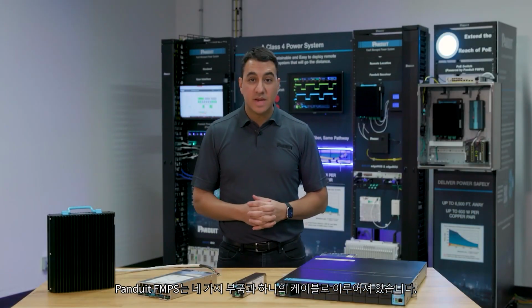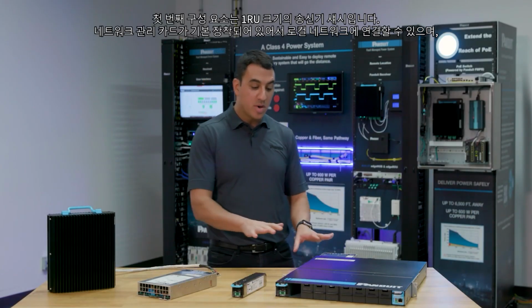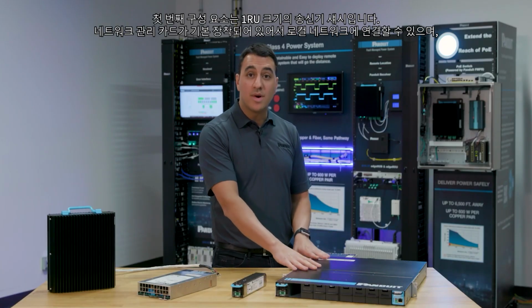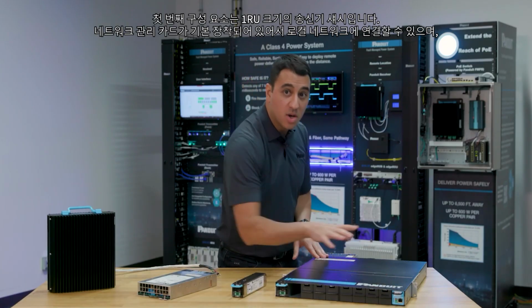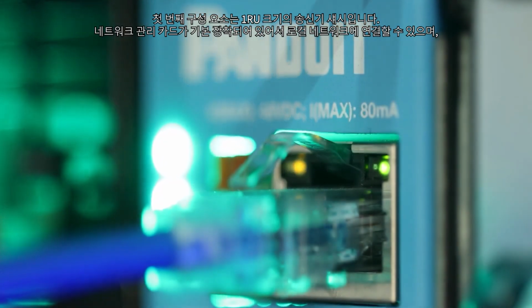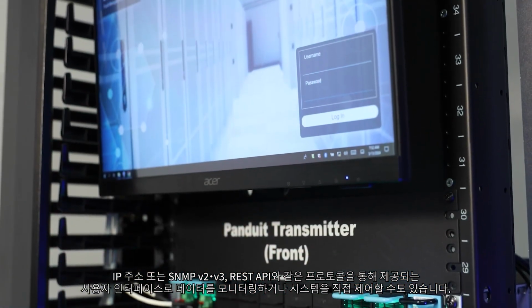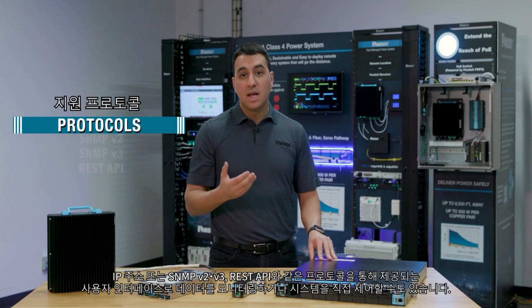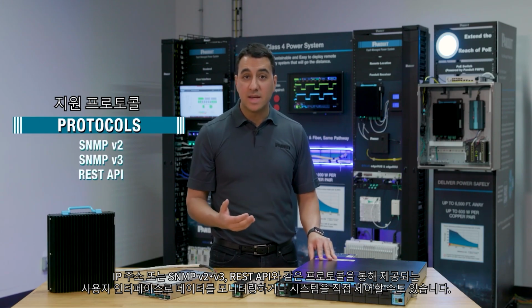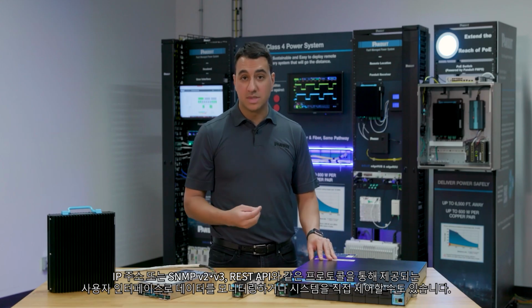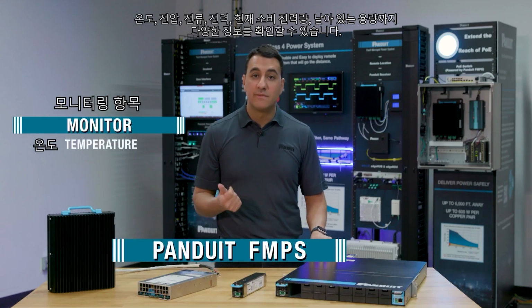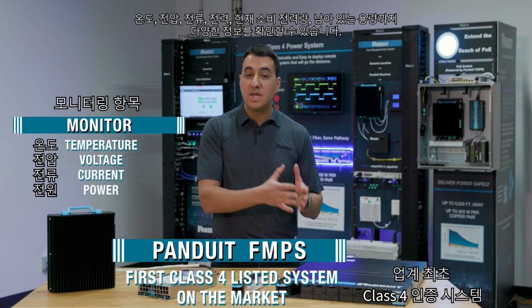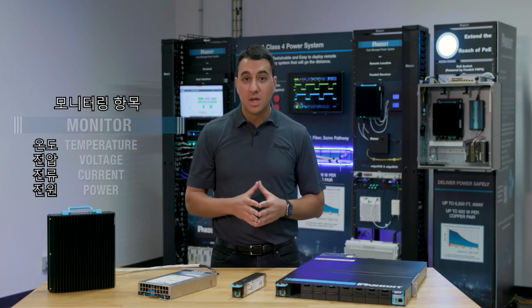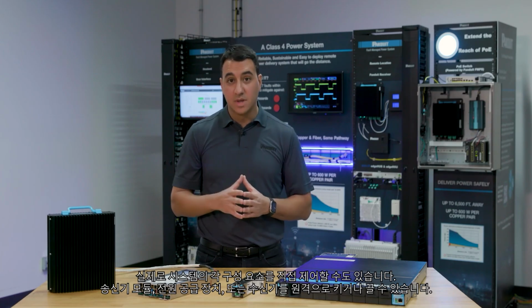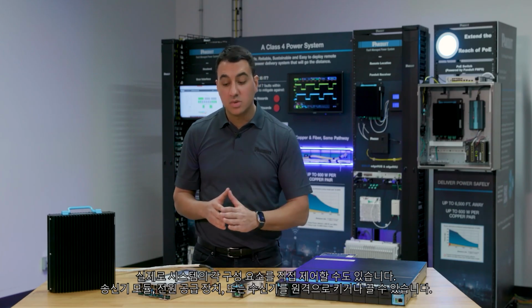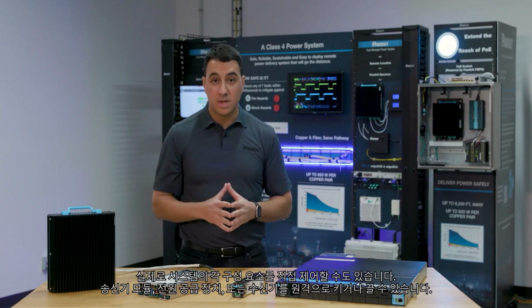The Panduit FMPS is made of 4 parts and a cable. The first part is a transmitter chassis, which is a 1RU unit. It comes with a network management card, which allows you to connect it to your local network, and through our user interface using an IP address or using protocols such as SNMP version 2, version 3, or REST APIs, you can monitor data or even control the system. You can monitor things like temperature, voltage, current, power, how much power is being consumed, and how much more capacity you have left. You can actually also control each part of the system. You can turn on or off the transmitter module, the power supply unit, or the receiver remotely.